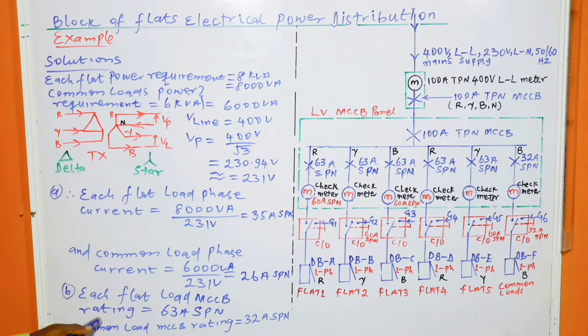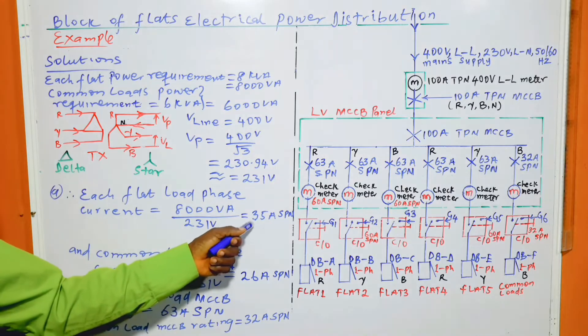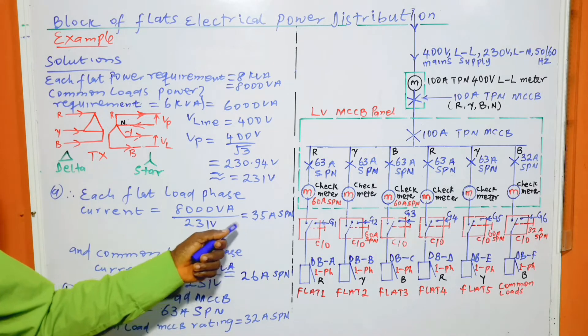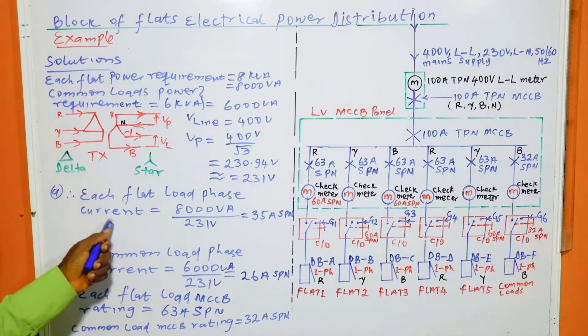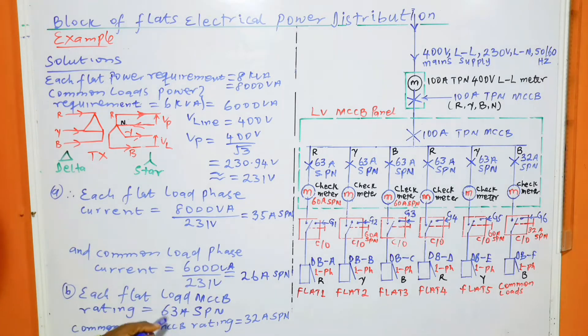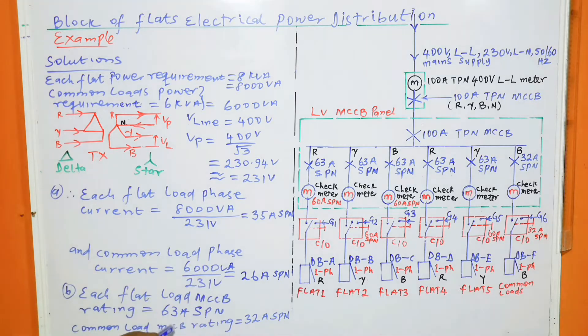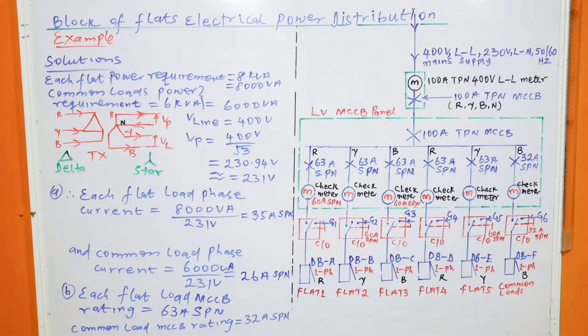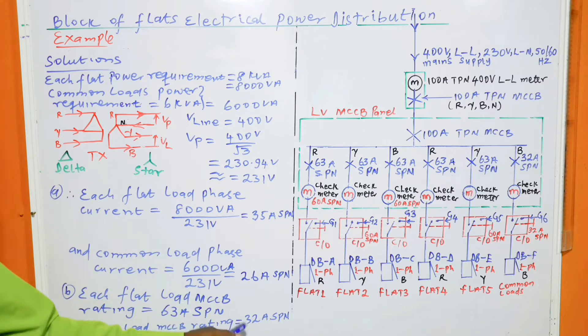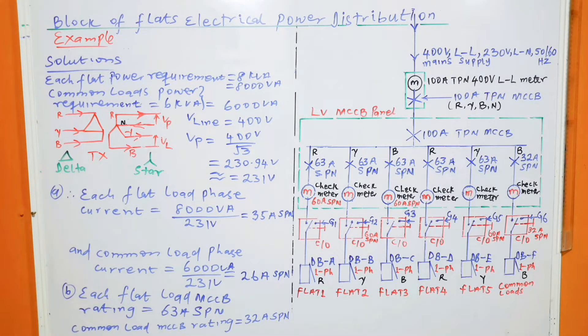Part B: each flat's load MCB rating is 63 amperes, single-phase with neutral. The calculated phase current was 35 amperes, and the nearest standard MCCB rating above that is 63 amperes. The common load MCCB rating is 32 amperes, which is the standard value slightly higher than the calculated 26 amperes but not lower than it.